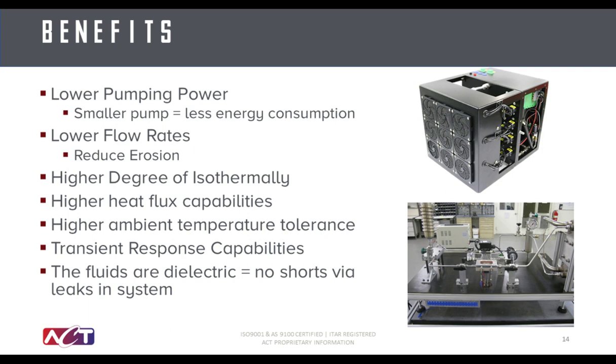Some additional benefits of pump two-phase cooling, apart from the lower pumping power and lower flow rates that we've already discussed: you can achieve higher degrees of isothermality across your components. Since the boiling process occurs at a constant temperature, all of the components seeing the saturated fluid will operate at close to the same temperature. For instance, if you had 5 chips all in the same coolant channel, the first chip and the last chip would see the same coolant temperature. That's not the case in a single-phase system, as the fluid picks up temperature as it flows across the heated components.